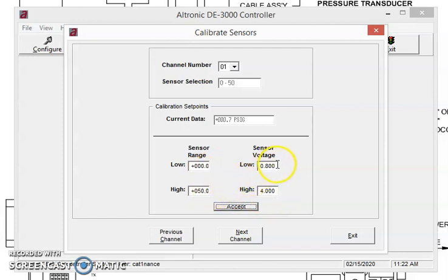So we're just going to tweak the low side real quick. Now I measured the voltage earlier, and I've already forgotten it, so I'm going to measure it real quick one more time. And I have 0.860 volts. So all I'm going to do is highlight this 0.86. I'm going to click out of that cell and I'm going to hit accept. It takes a second to refresh, but there we go. We're reading 0. So we do the same thing for the high side, just like the 0 to 5 volts, except we're dealing with 0.8 to 4 volts.